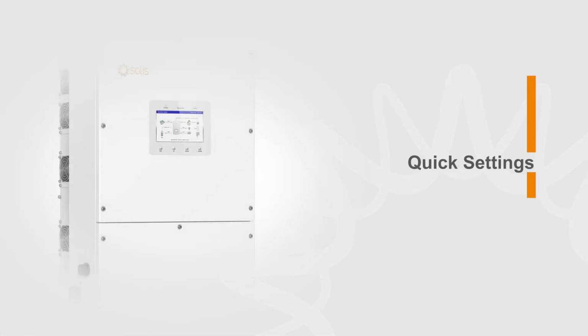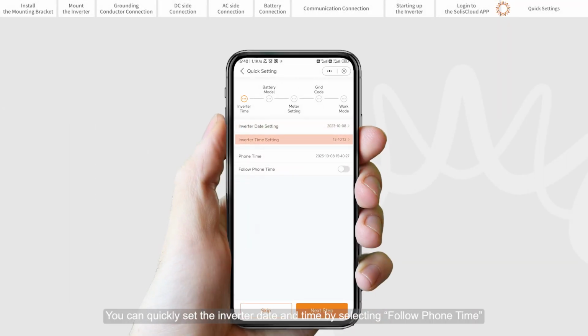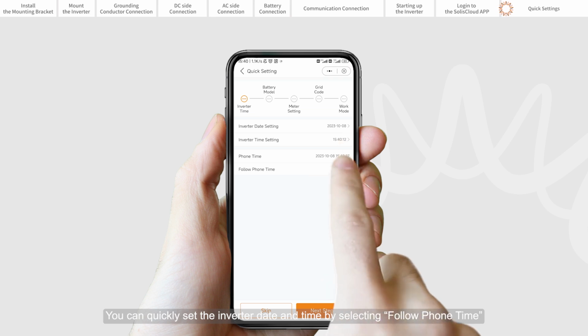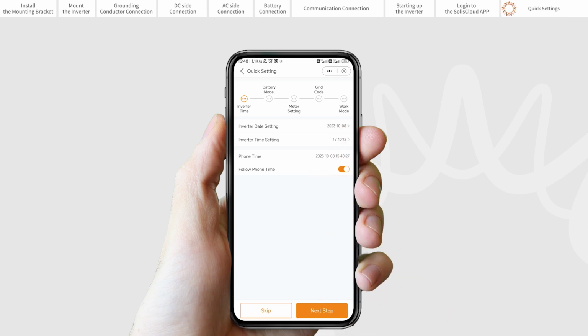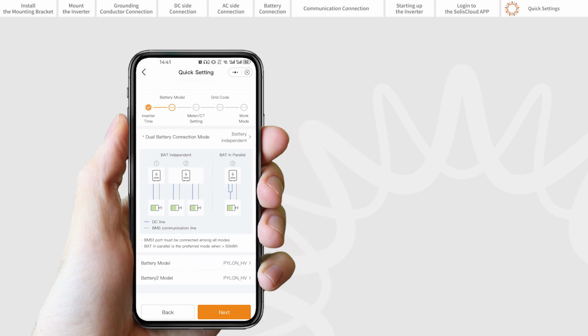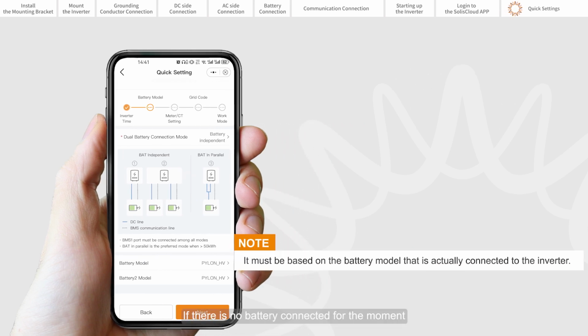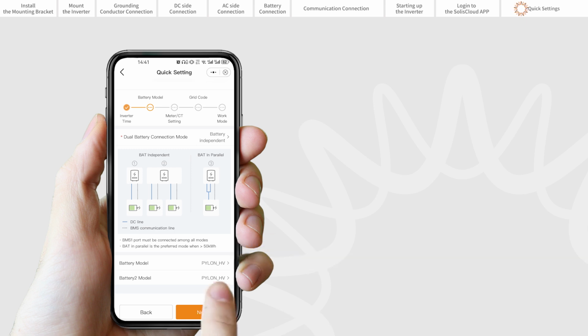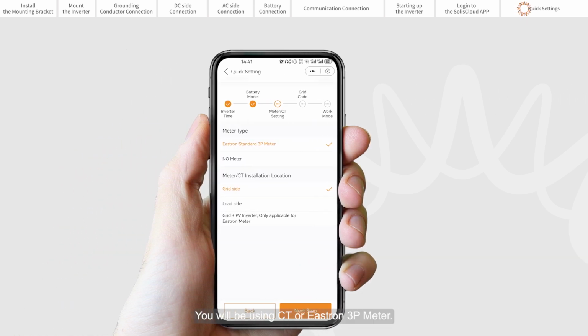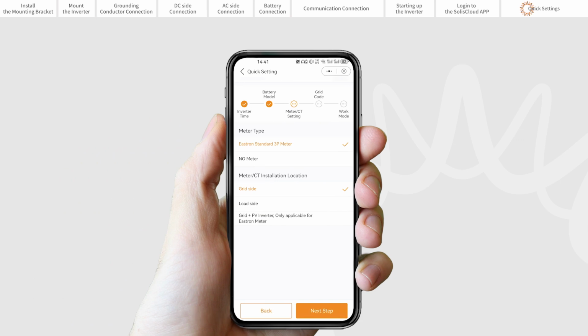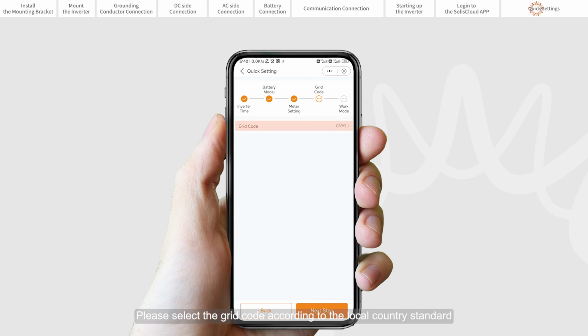Quick settings. You can quickly set the inverter date and time by selecting Follow Phone Time. Set the battery model. If there is no battery connected for the moment, please select No Battery to avoid alarms. You will be using CT or Eastron 3P meter. Set grid code. Please select the grid code according to the local country standard.